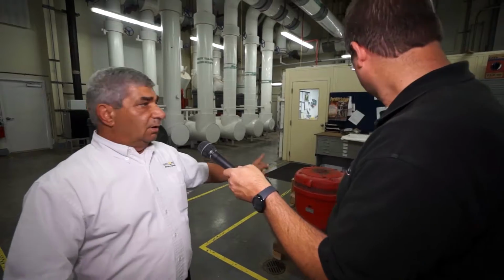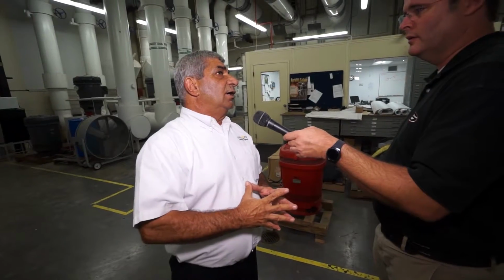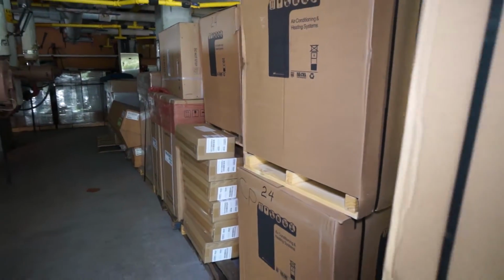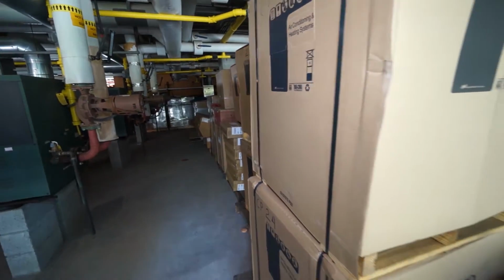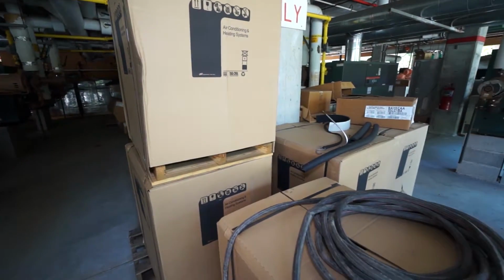So one pump going down is not going to be a detriment to everything. You've got enough redundancy to keep going. Oh, we have spare pumps. As you can see, there's one motor there that will take care of an evap. We have every spare part that we know we can change, because we're not going to order something and get it off the shelf and have it here tomorrow. So we have a spare pump for every size pump we have here, spare motors for our towers, we have seals, we have breakers. If the breaker fails, we can get up and going within a few hours.